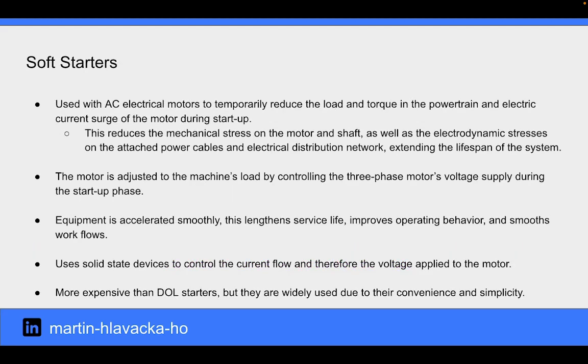A motor soft starter is a device used with AC electrical motors to temporarily reduce the load and torque in the powertrain and the electric current surge of the motor during startup. This reduces the mechanical stress on the motor and shaft, as well as the electrodynamic stresses on the attached power cables and electrical distribution network, extending the lifespan of the system.